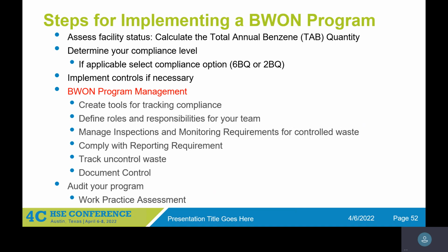Treatment processes, you have to do initial and quarterly visuals, and the ones that are less than atmospheric pressure, the ones that are in vacuum, in addition to doing the visual, you also have to do the non-detectable. And closed systems, you have to do initial and quarterly visual and initial and annual non-detectable. So a lot of people use their LDAR databases to track this kind of compliance.